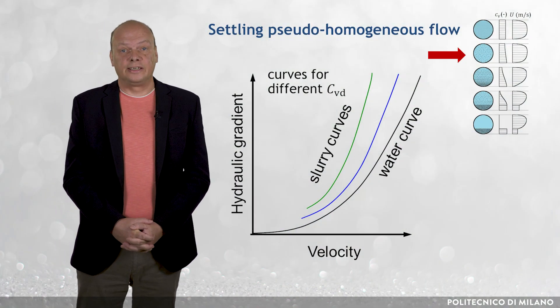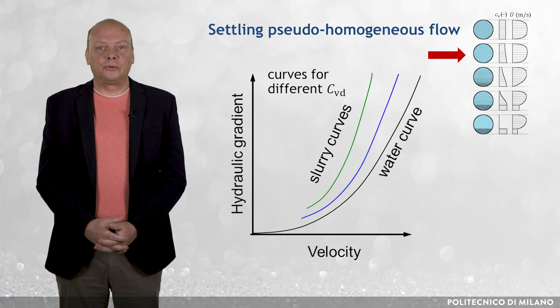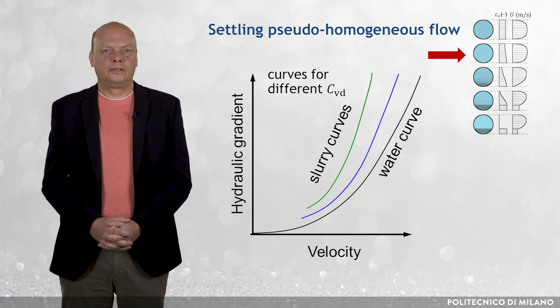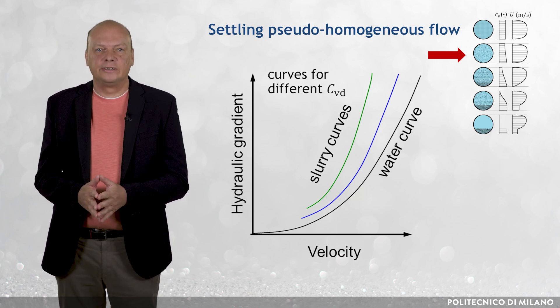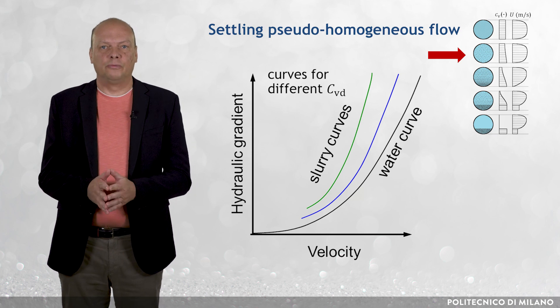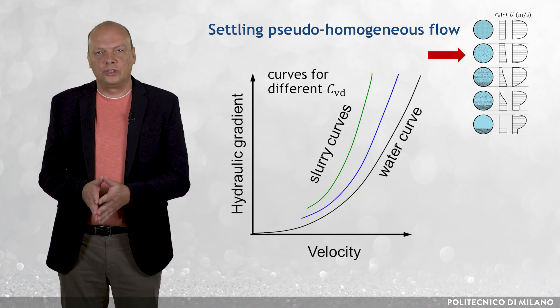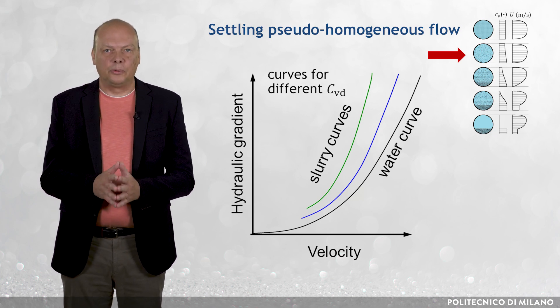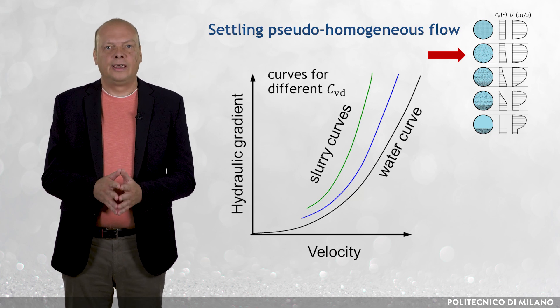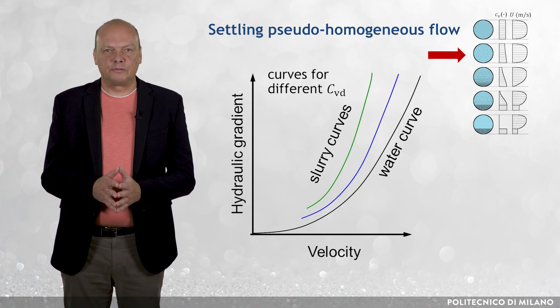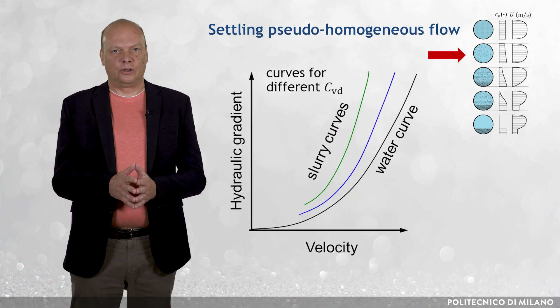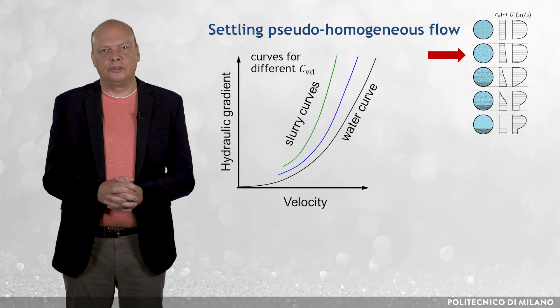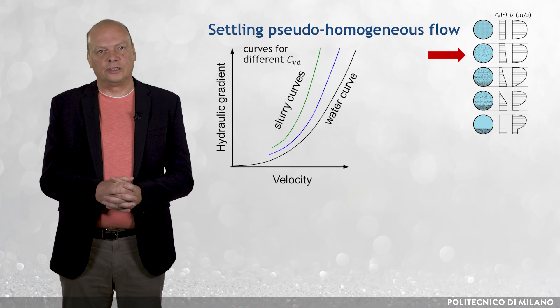In pseudo-homogeneous settling slurry flow, the pressure gradient increases with velocity in the entire range of flow velocities of practical interest. The variation in frictional hydraulic gradient follows a fluid-like form, meaning that particles are supposed to contribute to flow friction through their interaction with the carrying liquid — not through contacts with each other and with the flow boundary. The curves become steeper with increasing delivered concentration of solids, indicating that increasing these parameters increases the friction losses in a pipe.